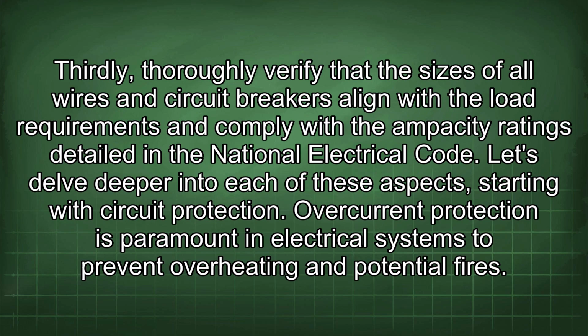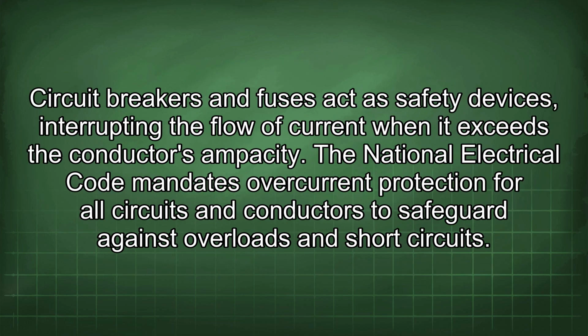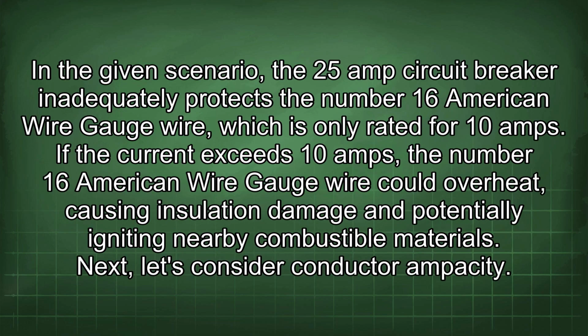Overcurrent protection is paramount in electrical systems to prevent overheating and potential fires. Circuit breakers and fuses act as safety devices, interrupting the flow of current when it exceeds the conductor's ampacity. The National Electrical Code mandates overcurrent protection for all circuits and conductors to safeguard against overloads and short circuits. In a given scenario, the 25 amp circuit breaker inadequately protects the number 16 American wire gauge wire, which is only rated for 10 amps. If the current exceeds 10 amps, the number 16 wire could overheat, causing insulation damage and potentially igniting nearby combustible materials.